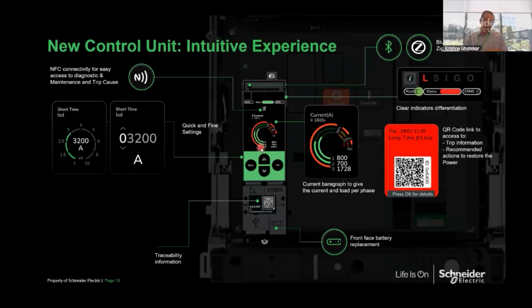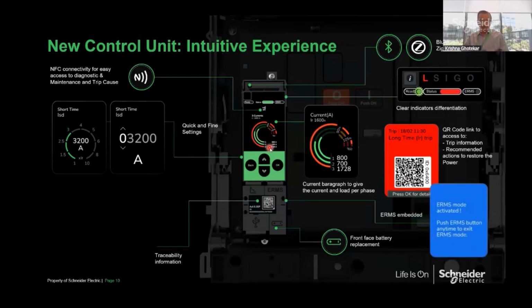For other different breakers, first of all, you have to add multiple accessories and software to get ERMS, and then you have to add another hardware switch to activate or deactivate this function. But here it's much more user friendly. Open the flap, activate. Once the operator finishes work in the electrical room, while leaving, he again presses the ERMS button and the breaker will go back to its original settings. So this is the ERMS button, and the display in ERMS mode will be blue in color. Plus this ERMS LED will glow, to indicate that the breaker is in the ERMS mode.